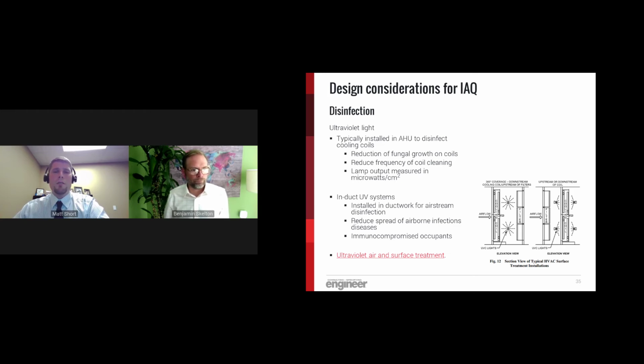When specifying UV lights, be sure to consider the cooling coil, UV light, and final filter arrangement. UV light can degrade a filter if there's not enough distance between the lamps and the filter. This is most prevalent in a blow-through unit orientation, where the fan section is not present to provide adequate spacing between the coils and final filter.